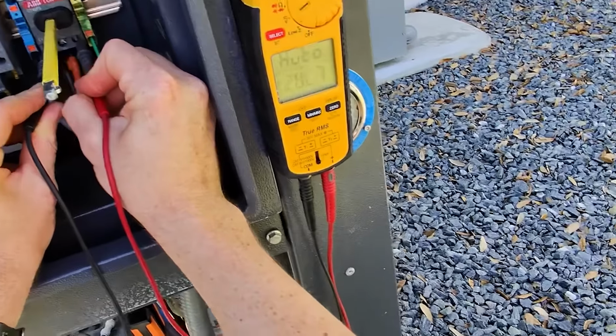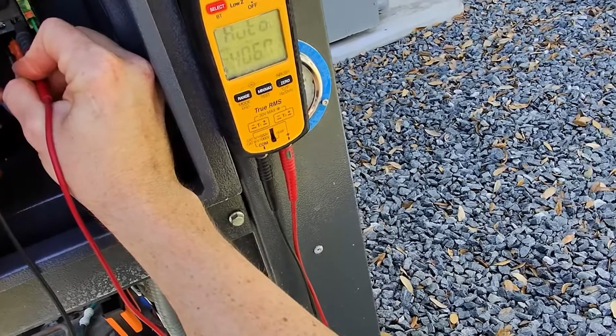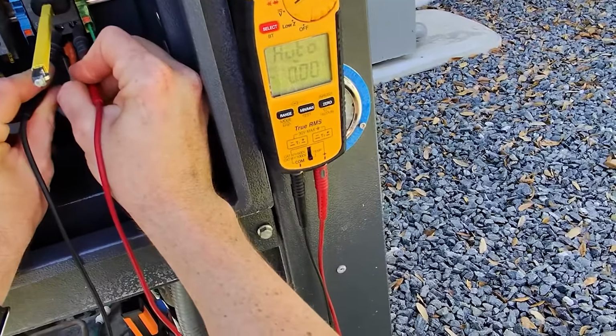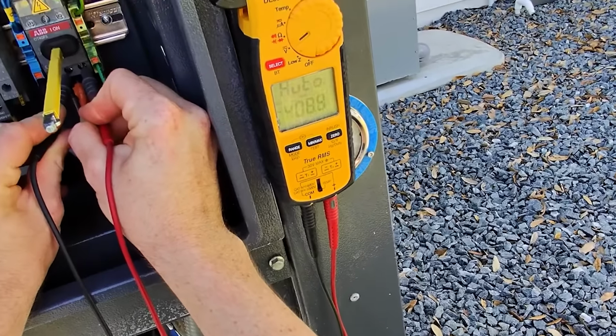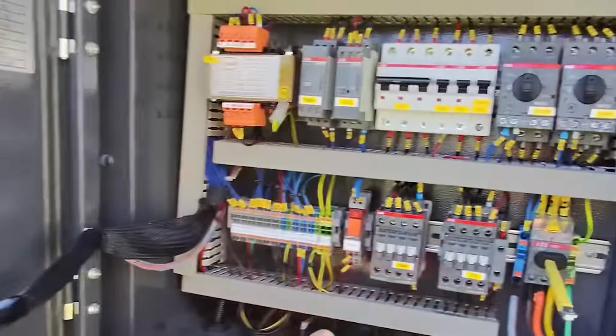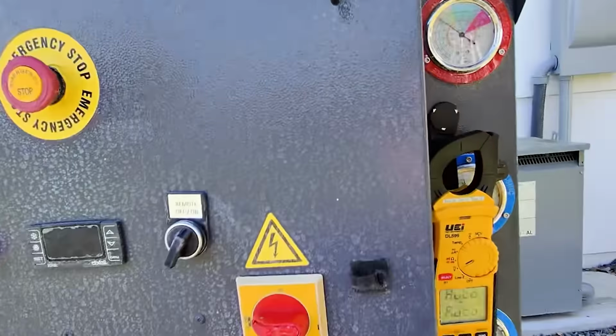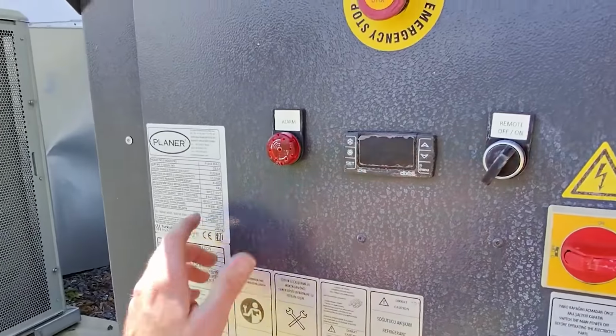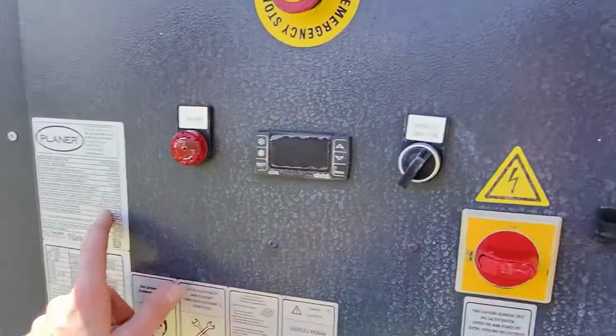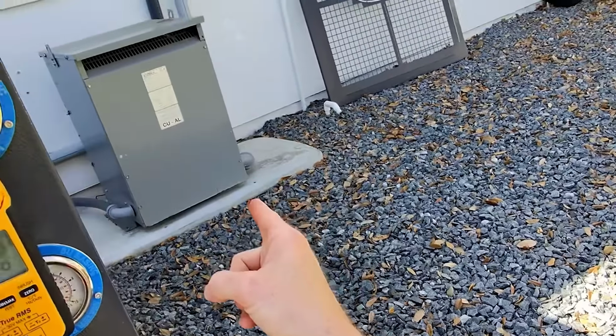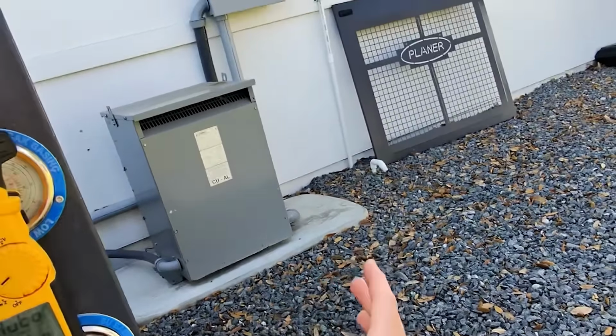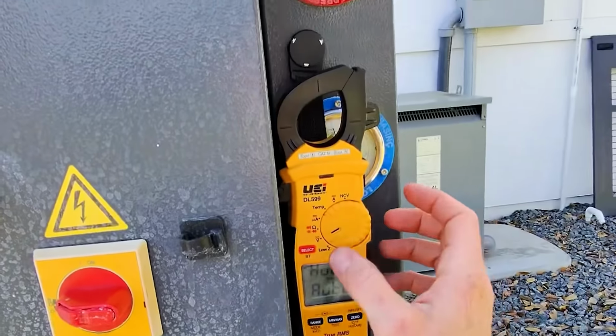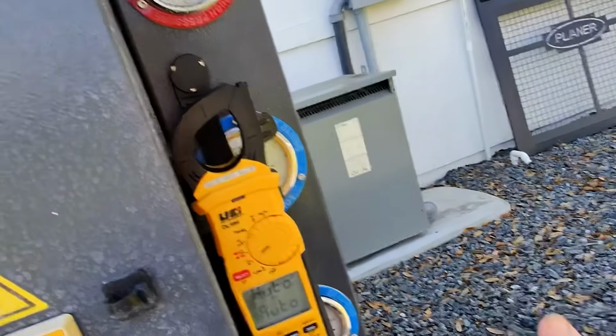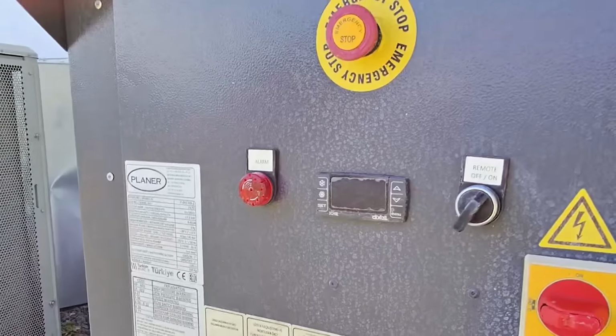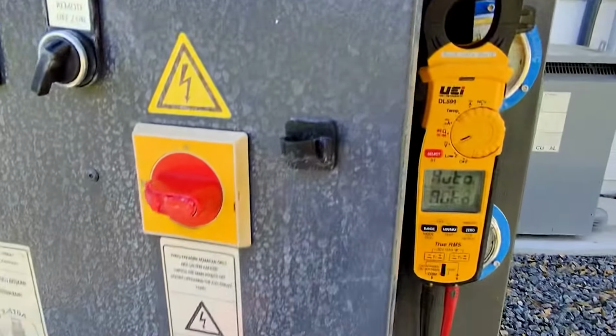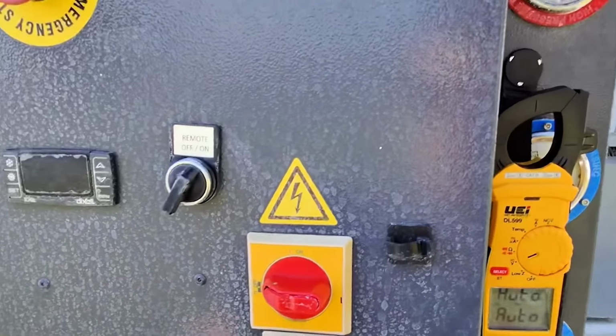406 volts, 406 volts, 409 volts. So not your average piece of equipment. This isn't even on 208, 240. So I would even guess, based upon the voltage I see here, right, we are wired for 400 volts, well, 380 from what it says here. That guy over there in the corner was put in just to feed this piece of equipment outside of our market to make this 50 hertz at 400 volts, something you're not going to see out in the wild for air conditioning systems. So now I know the voltage.